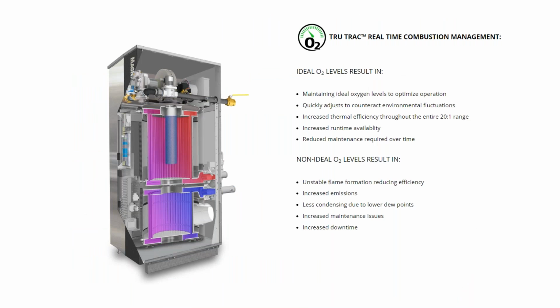So let's talk about TrueTrack O2 trim combustion management. So what does it really do? It's going to maintain the oxygen levels to optimize the operation, right? So it quickly adjusts to counteract environmental fluctuations throughout the whole range. It increases the runtime availability by eliminating a lot of the sooting problems we get, and it reduces your maintenance over time. What happens if we don't do this? We'll get an unstable flame formation which will reduce our efficiency.